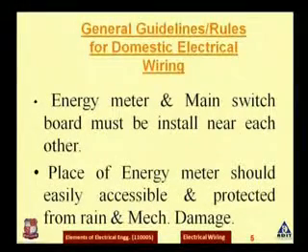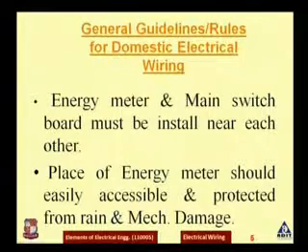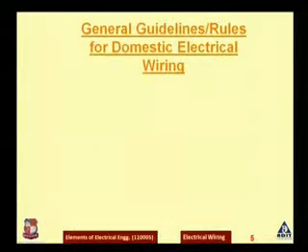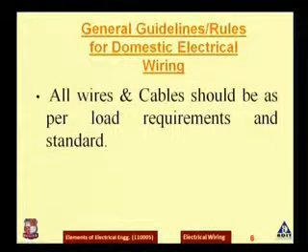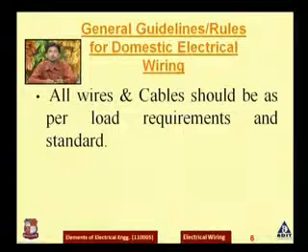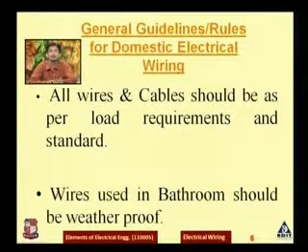The second guideline is that the energy meter should be easily accessible and protected from rain and mechanical damage — it should not be placed in an open area, otherwise it may get damaged by rain. The third guideline is that all wires and cables used for electrical wiring should meet load requirements and electrical standards. Wires used in the bathroom should be waterproof, and if doing wiring on the terrace, PVC cables must be used.